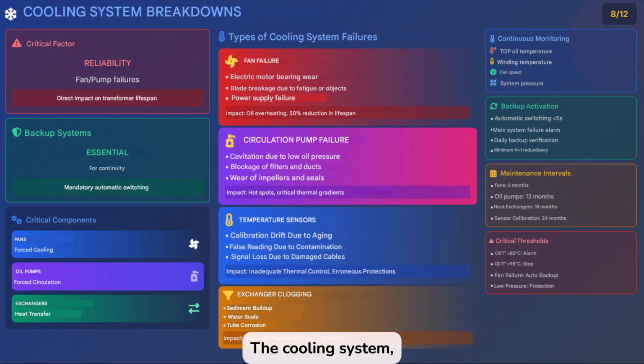The cooling system, often underestimated, is essential to preserving the transformer's lifespan. Although it doesn't cause immediate failures, malfunctions cause heat buildup that accelerates the aging of internal materials. This silent degradation impacts both the technical performance and the financial depreciation of the asset. Loss of cooling reliability directly affects operational continuity. Failures in fans or pumps disrupt thermal balance, causing overheating that can reduce transformer lifespan by up to 50%. This translates into additional costs for early replacement and a reduction in expected payback.